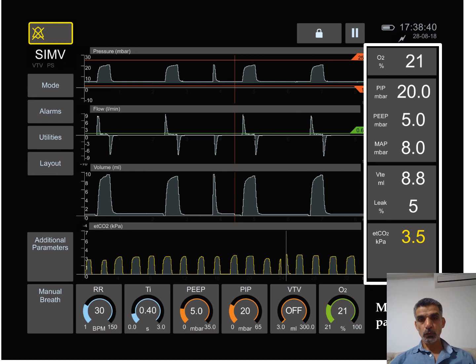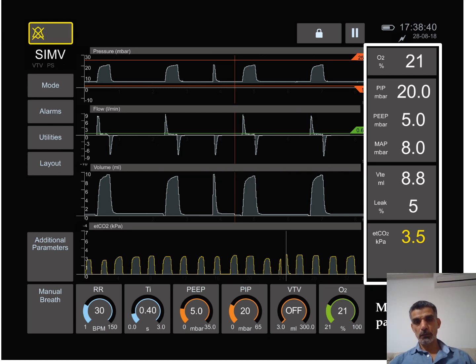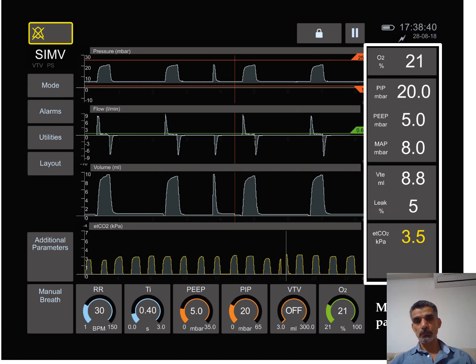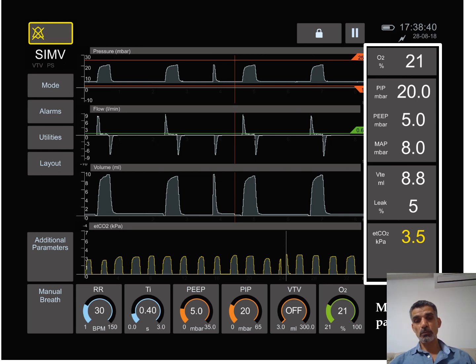We also see a number of numbers in sidebars and this is not what we set, but what is measured by the ventilator. So we set 21 percent of O2, but this tells us how much actually oxygen is going to the baby.